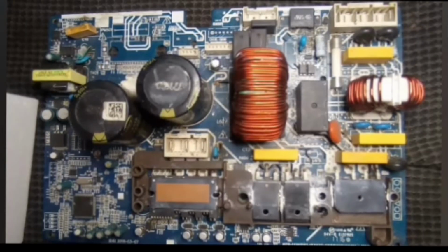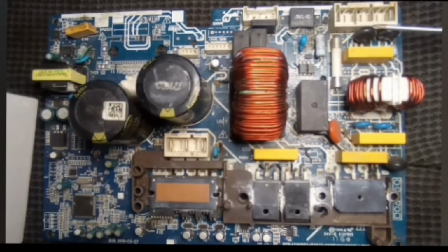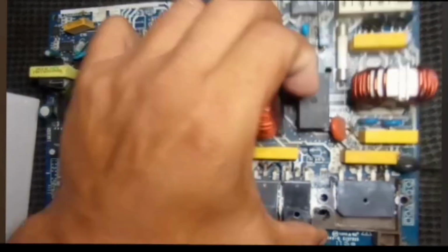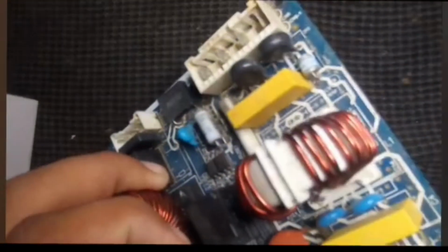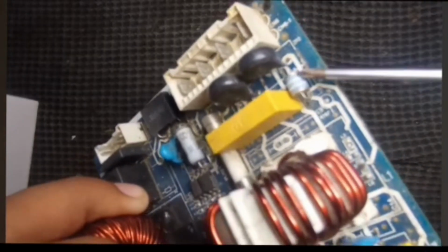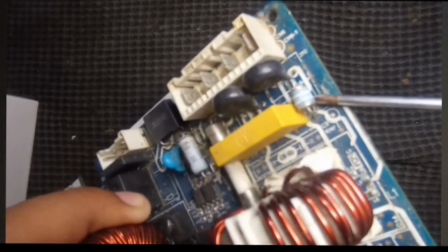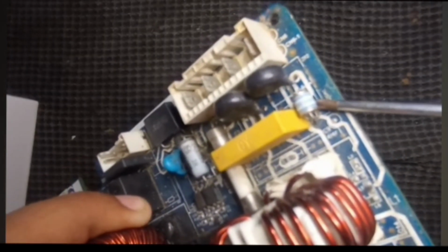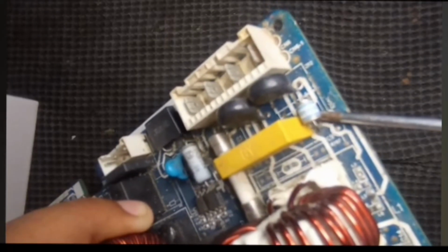So, the fuse protects us against a current increase, and the varistors protect us against a voltage increase. We also have this instrument, which is called GDT, which is a gas discharge tube. And it serves to protect against overvoltages, acting in conjunction with the varistors.